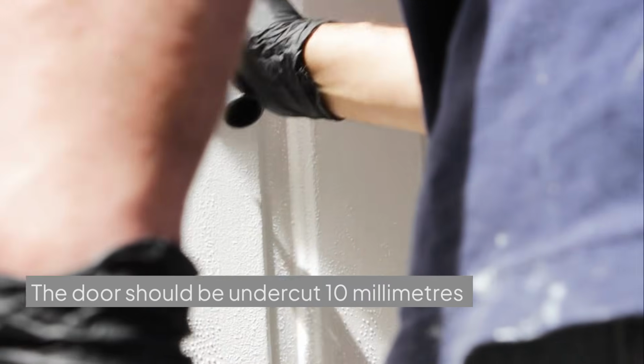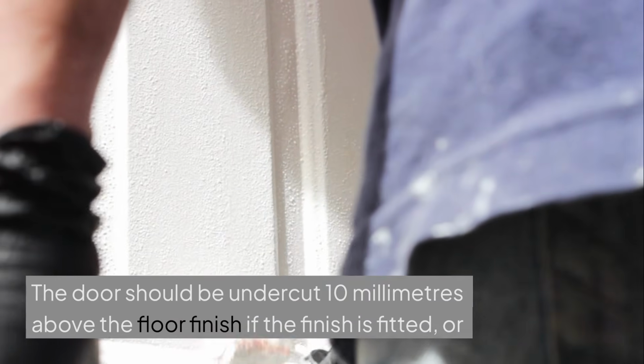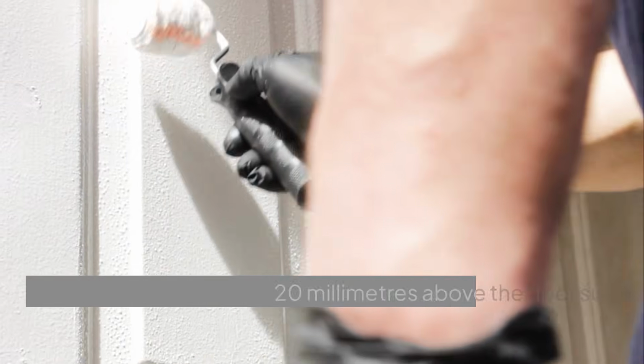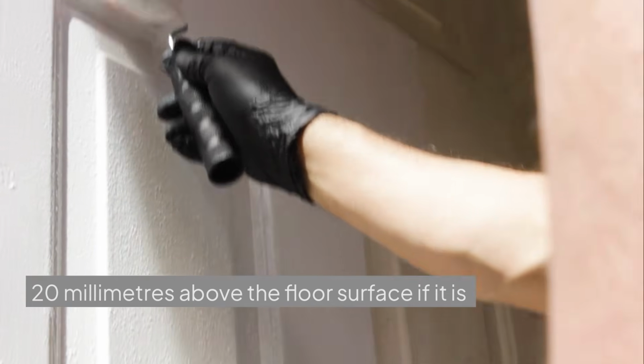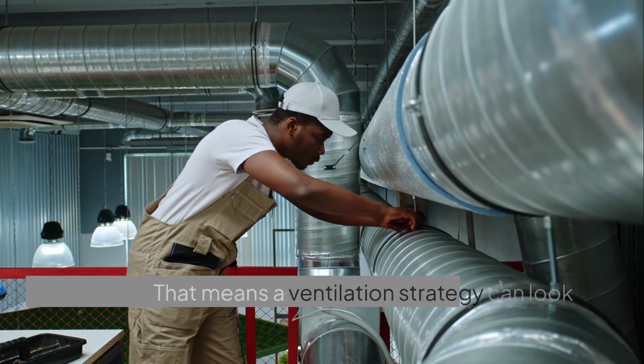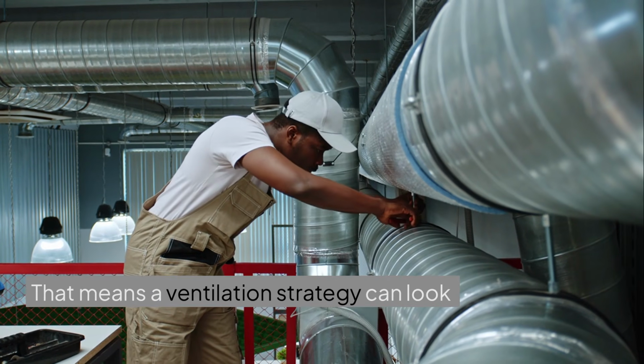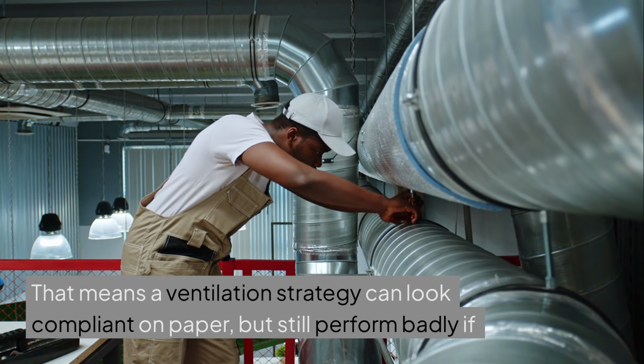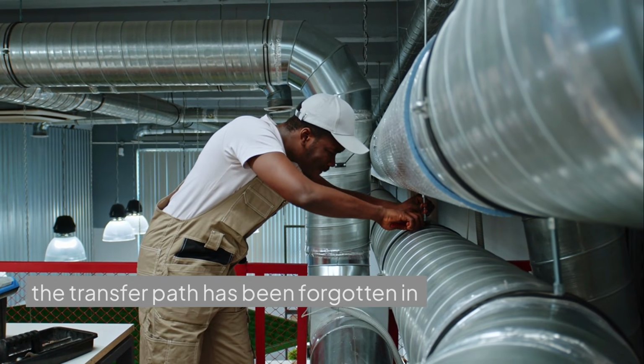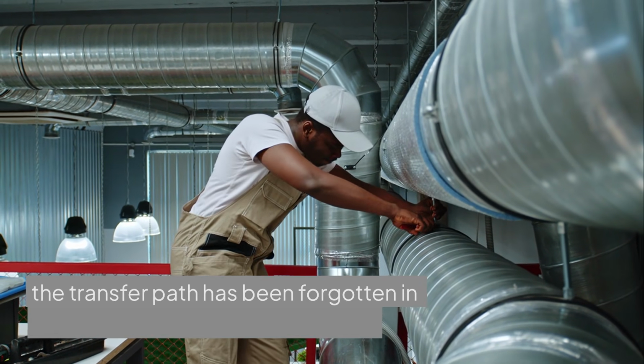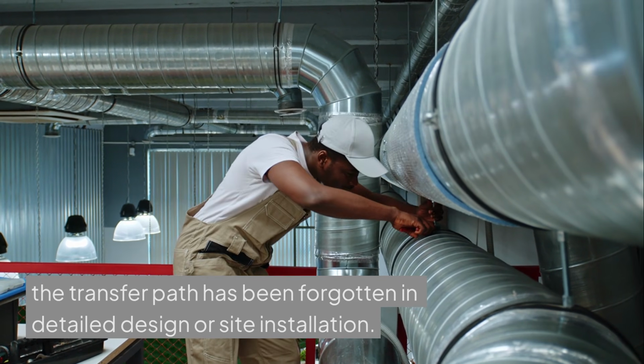The door should be undercut 10 mm above the floor finish if the finish is fitted, or 20 mm above the floor surface if it is not yet fitted. That means a ventilation strategy can look compliant on paper, but still perform badly if the transfer path has been forgotten in detailed design or site installation.